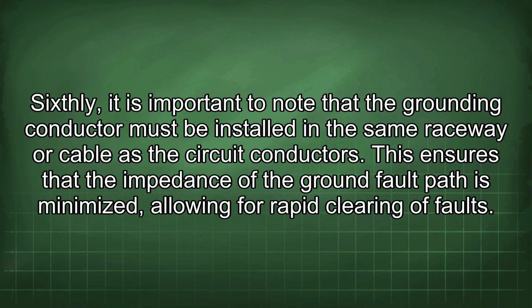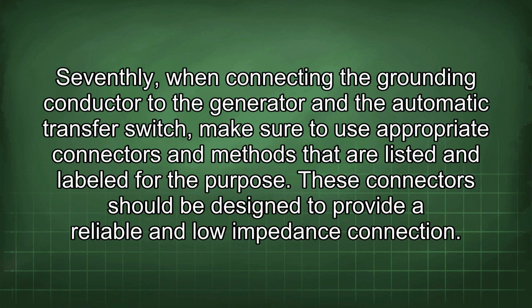Sixthly, it is important to note that the grounding conductor must be installed in the same raceway or cable as the circuit conductors. This ensures that the impedance of the ground fault path is minimized, allowing for rapid clearing of faults. Seventhly, when connecting the grounding conductor to the generator and the automatic transfer switch, make sure to use appropriate connectors and methods that are listed and labeled for the purpose. These connectors should be designed to provide a reliable and low impedance connection.